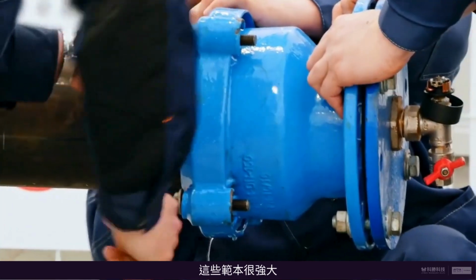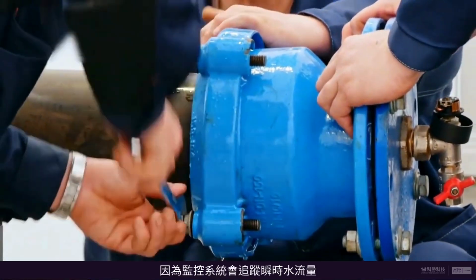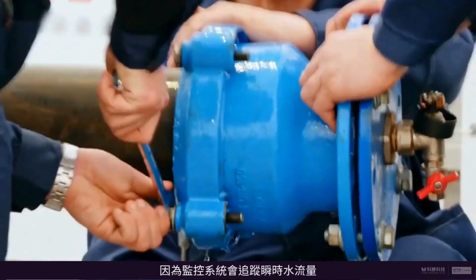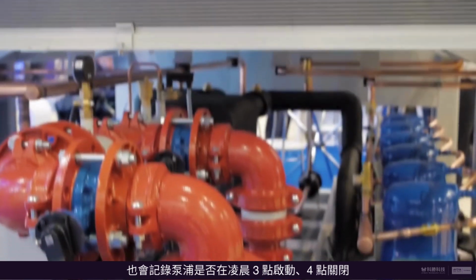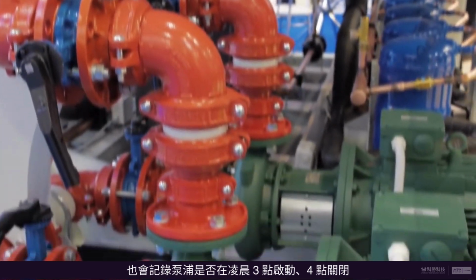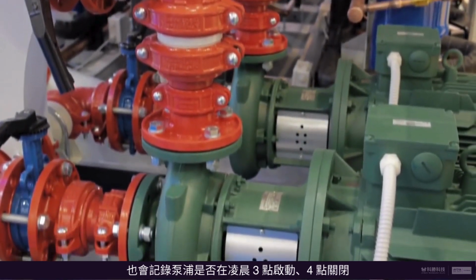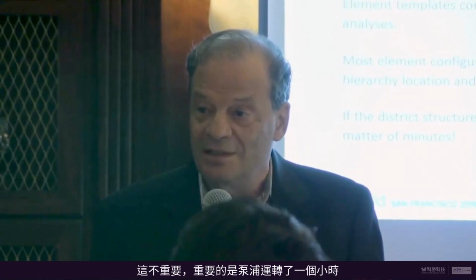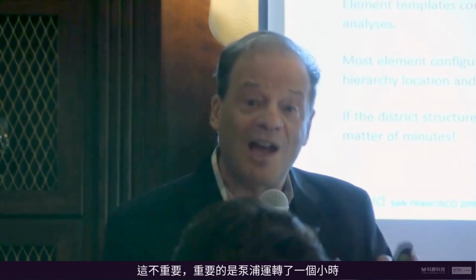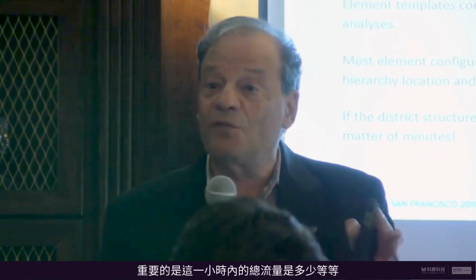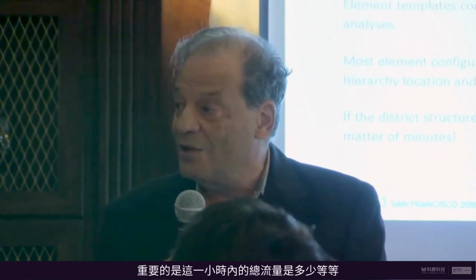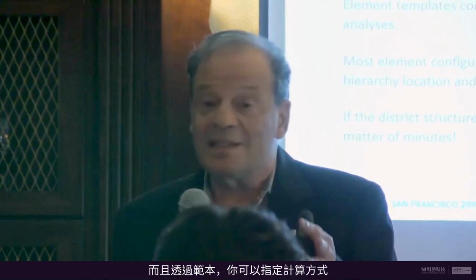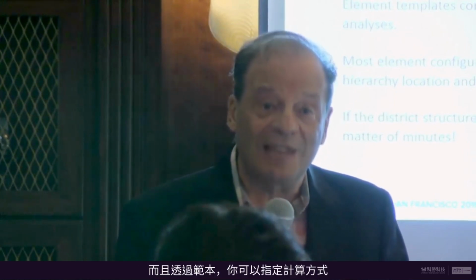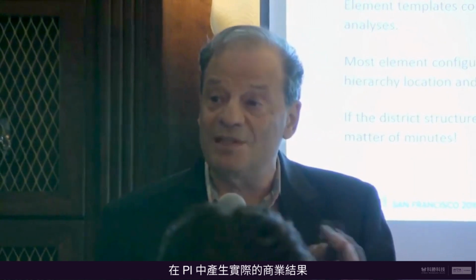Now, these templates are powerful because the SCADA system keeps track of the instantaneous water flow, and it keeps track of whether, like, a pump started at 3 a.m. and turned off at 4 a.m. That's not interesting. What's interesting is the pump was on for an hour. What's interesting is the total flow over the period of time in that hour was such and such. And with the template, you can specify the calculation that actually produces the business result.